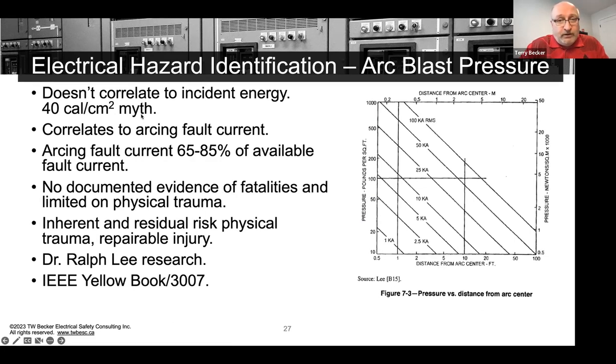There's what I call the 40 cal myth. This has been going on for a decade too. The myth says that if the incident energy is 40 cals or greater, we can't do any work energized because the blast pressure is going to be extremely high. It was completely wrong. His research from 1988, 89-ish validated that.